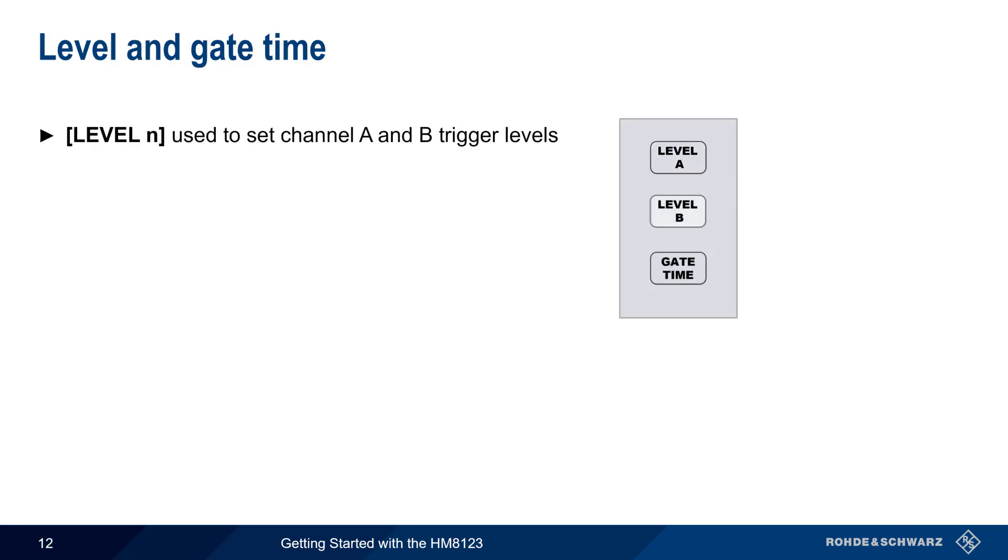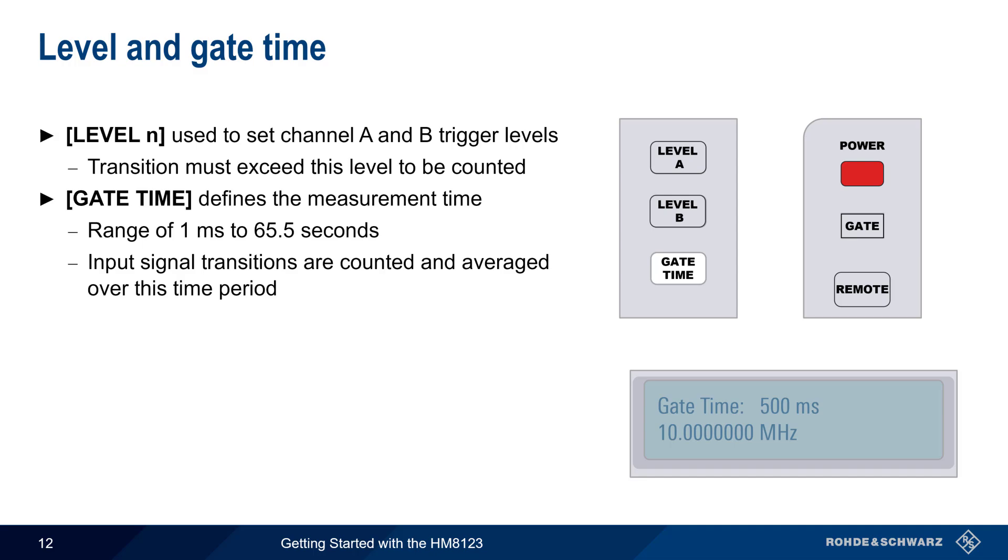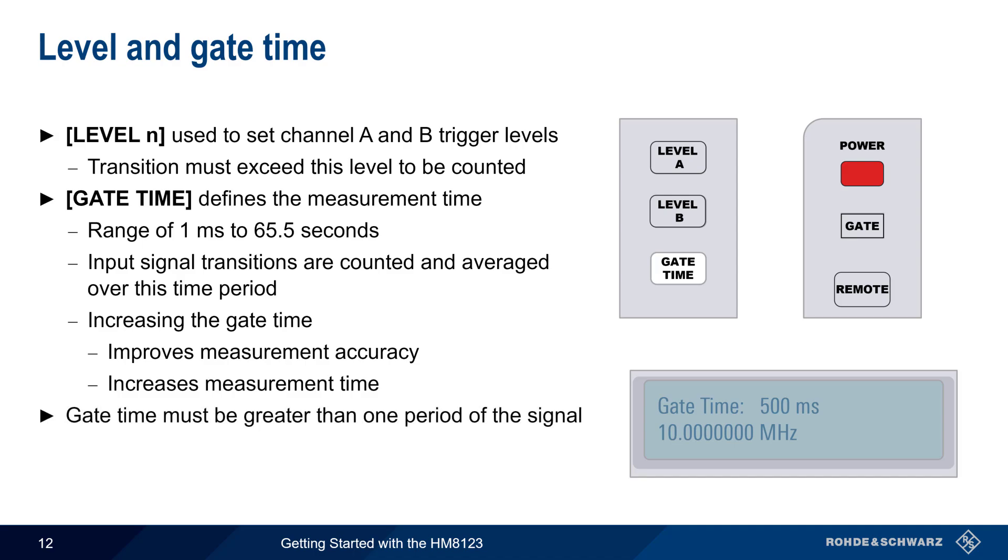The level A and level B keys are used to set the channel A and channel B trigger levels. The measured voltage transition must exceed this level to be counted. Gate time can be set to the range of 1 millisecond to 65.5 seconds. Input signal transitions are counted and averaged over this time period. Increasing the gate time will improve measurement accuracy, but will also increase the time needed to obtain a measurement result. Note that the gate time must be greater than one period of the signal. When the gate is open, the gate LED beneath the power button will be illuminated. So it's normal to see this light flashing during operation.